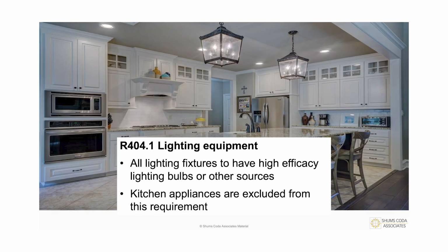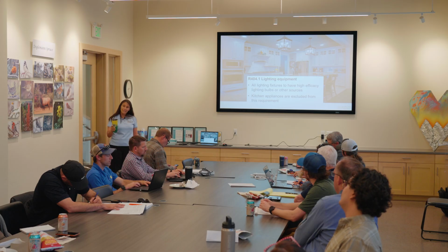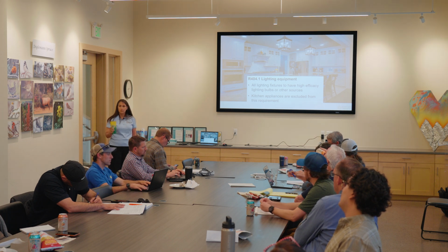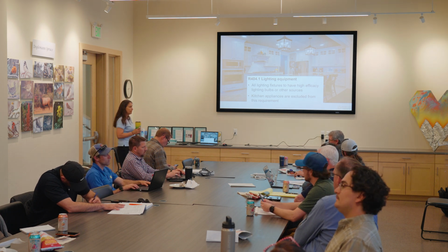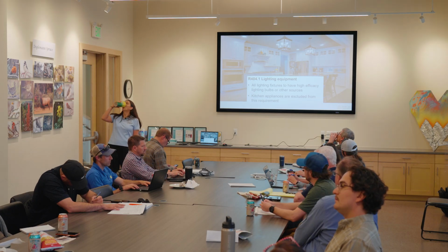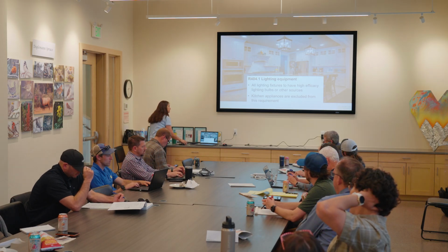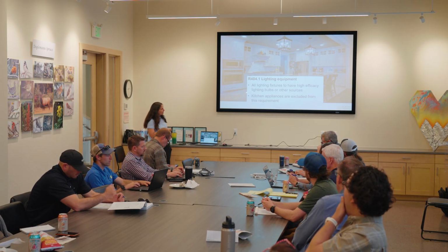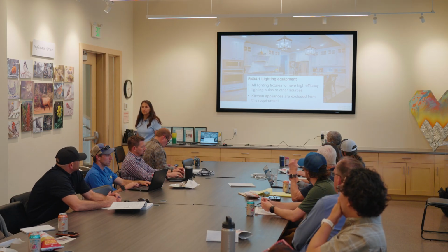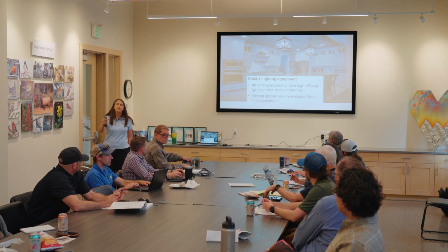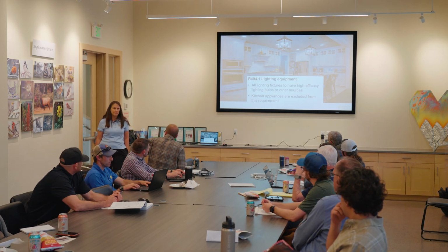Although I don't know of very many manufacturers that are manufacturing things that are no longer permitted by code, that doesn't mean that there isn't new or old stock in play. By the way, that is not an energy code criteria. It's a federal efficiency change. State laws are complying with what the federal mandate is. Now, kitchen appliances are exempt from that. So the light in the refrigerator, the light in the stove, all of those are exempt for the time being.